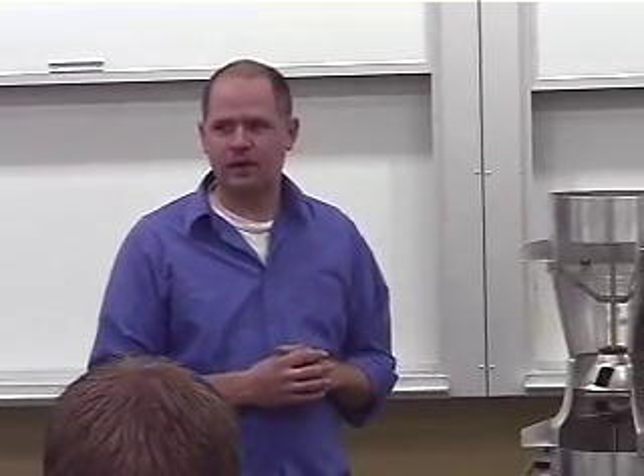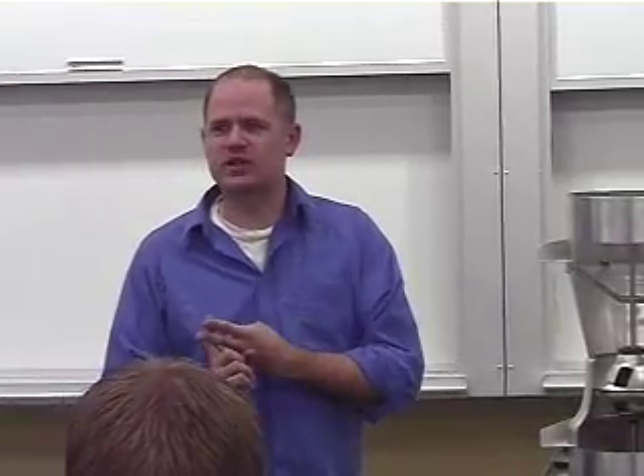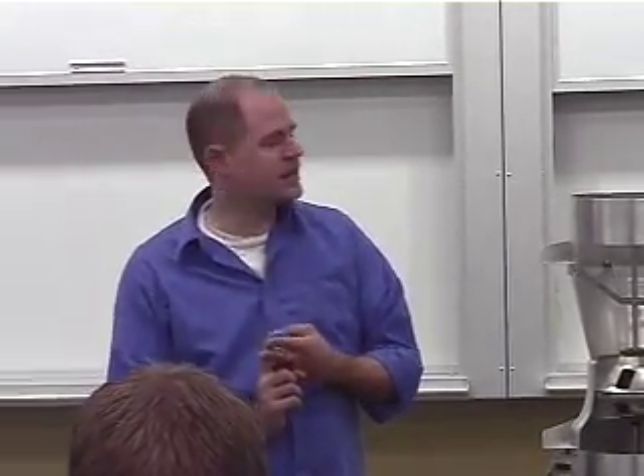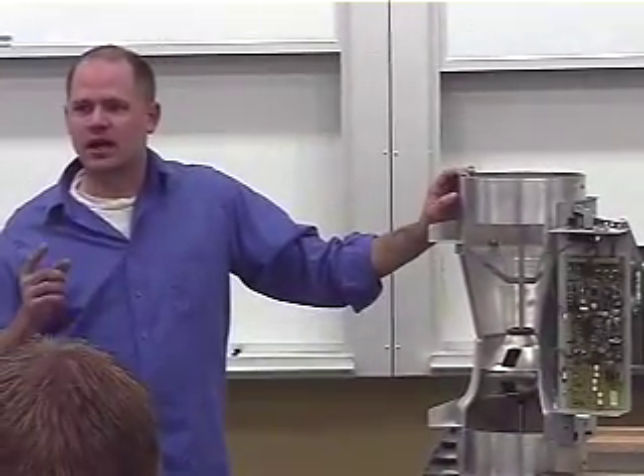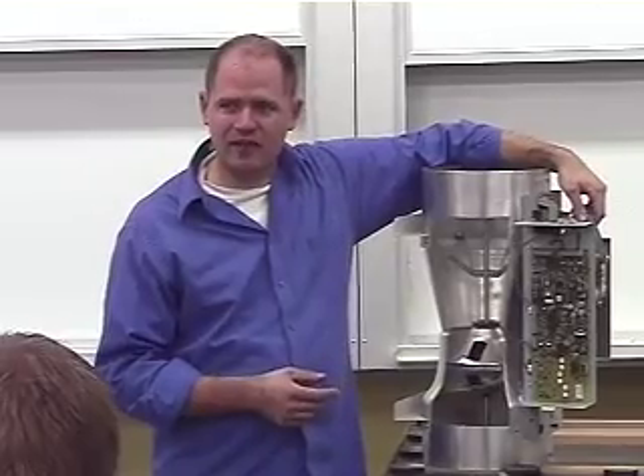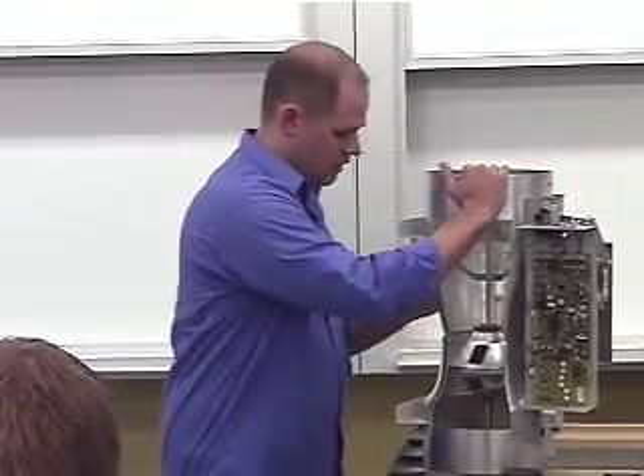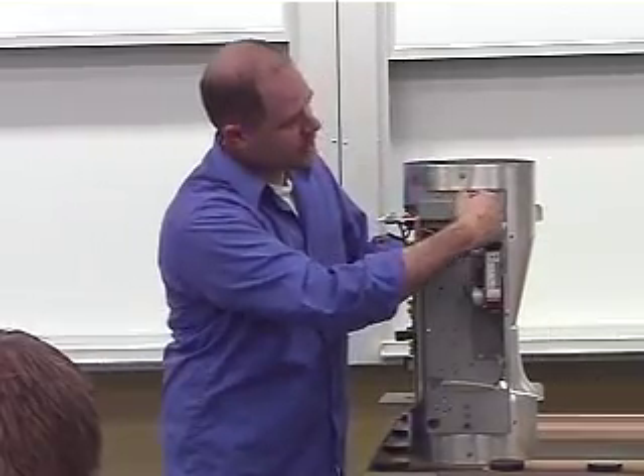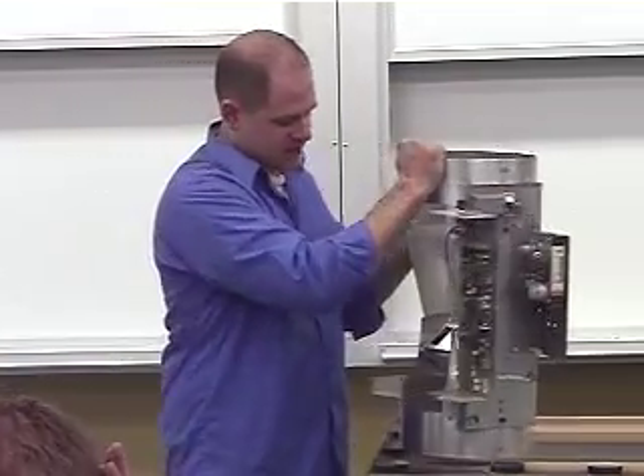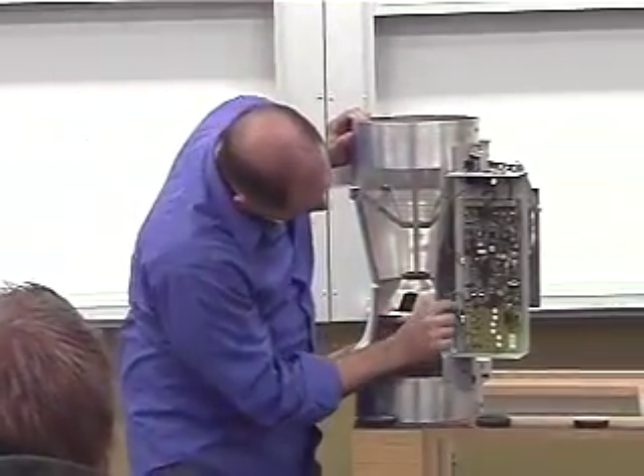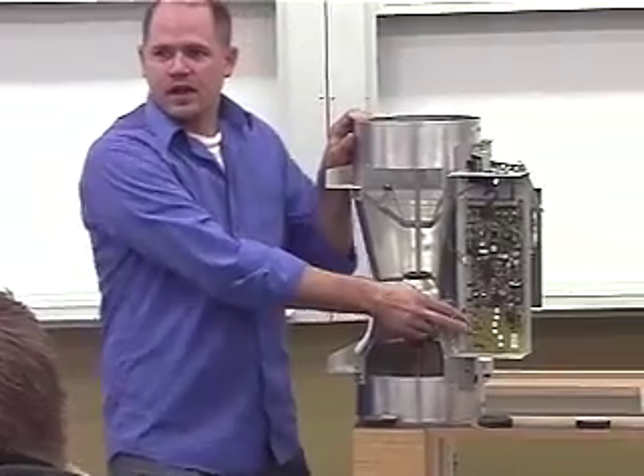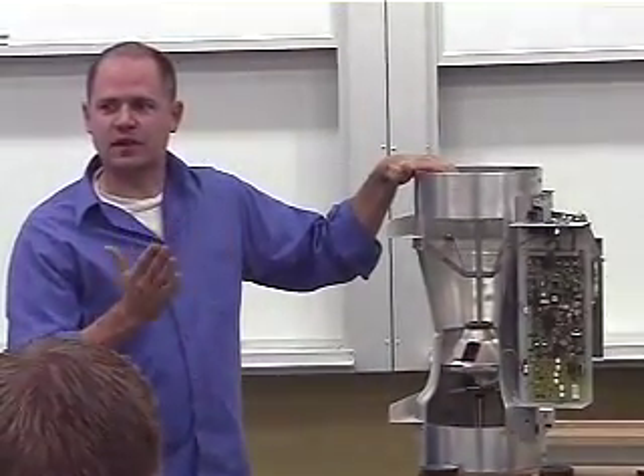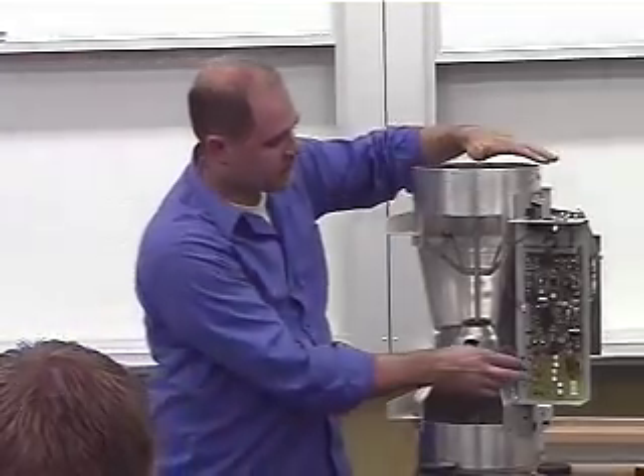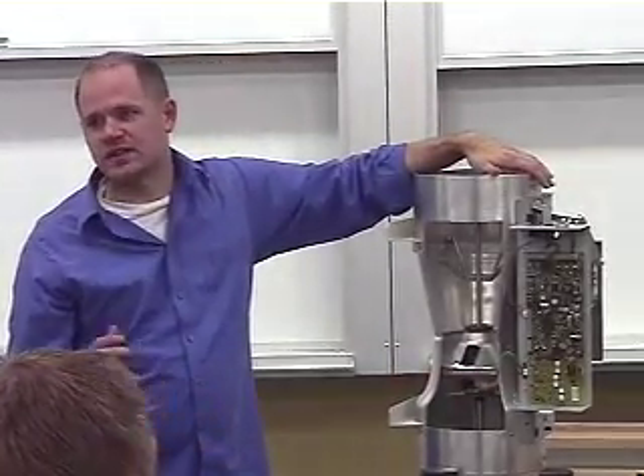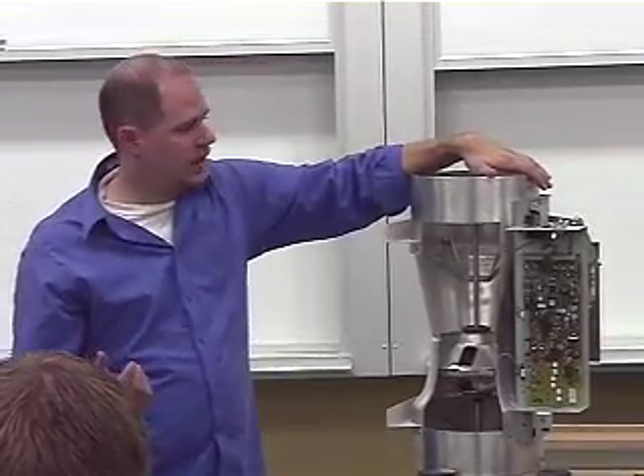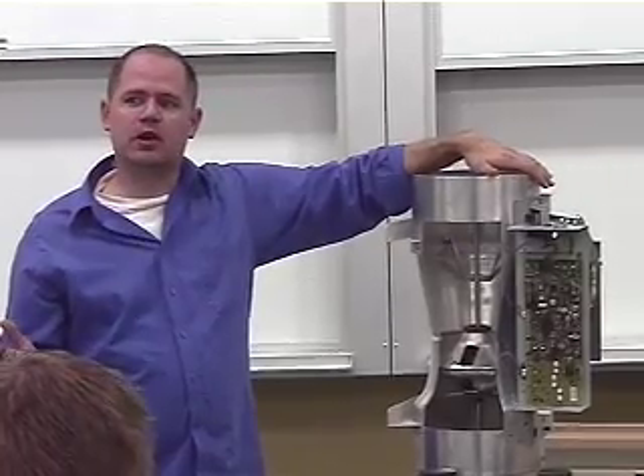Typically what they'll have is a flow alarm and a jam alarm, the two types of alarms. A flow alarm indicates that the pressure drop across the valve is not being met. A jam alarm means that it's trying to drive the valve, but the valve does not appear to be moving. Every one of these has a potentiometer in this little piece right here that feeds back a resistance value into this circuit board. That way, as it rotates that arm, it knows exactly what position the arm is in. It sends a voltage through it, so it gets a voltage signal back indicating it's open to a certain level, and there's a flow curve programmed into each of these.